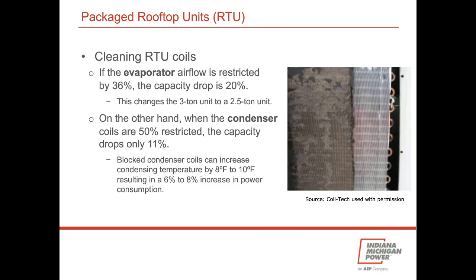Just a word about cleaning coils. The evaporator coil is much more sensitive to cleanliness than the condenser coils. And there have been some studies, and they determined that if the evaporator airflow is restricted by a third, capacity drops by about 20%. So a 3-ton unit would now become a 2.5-ton unit. On the other hand, when the condenser coils are 50% restricted, quite a bit more than what we gave just now, the capacity drops only about 11%. But 11% is still pretty significant. Just realize that the evaporator coil is a lot more sensitive than the condenser coils.